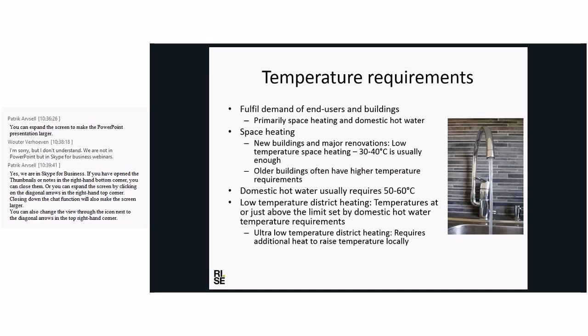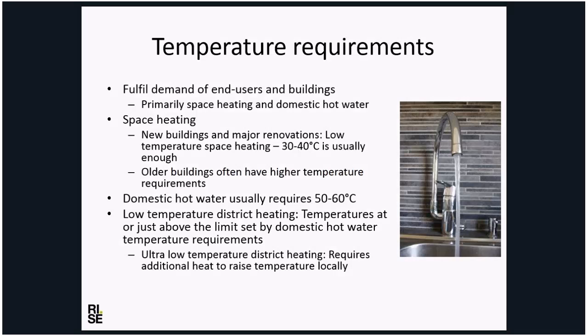For domestic hot water, we need around 50 to 60 degrees Celsius usually. This also differs among requirements in different countries. Usually the limit is set by the fear of growth of Legionella bacteria. I could mention that we currently have an ongoing project which is investigating one type of technology to reduce the risk and produce safe hot water even at slightly lower temperatures by avoiding circulation and storage of hot water.